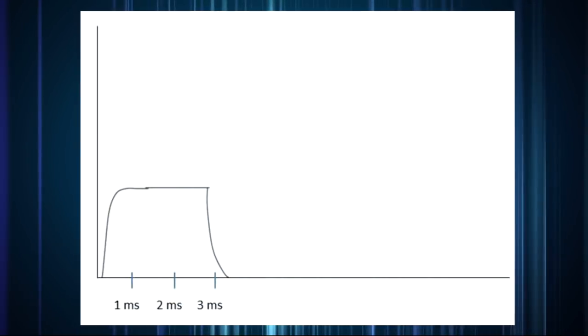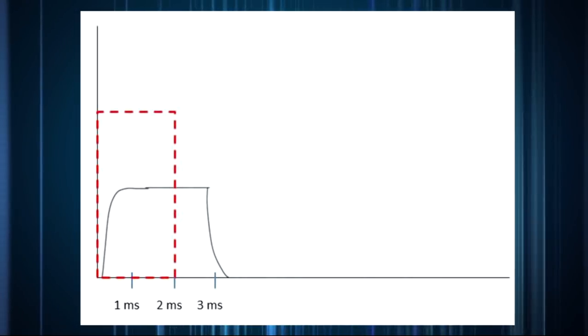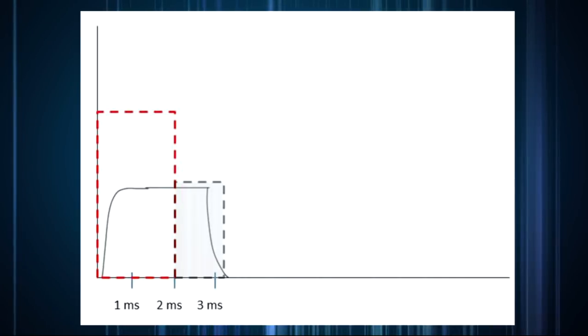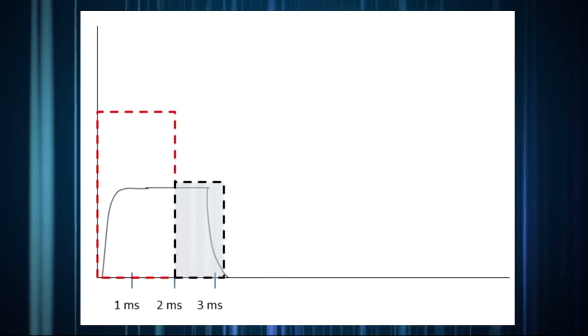If the laser pulse is actually longer than, for example, 2 milliseconds, yet one sets the maximum pulse width to the 2 millisecond setting, some of the pulse will be cut off and ignored, resulting in an incorrect reading.